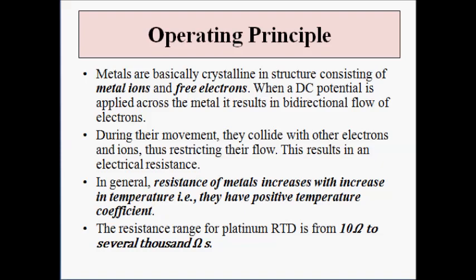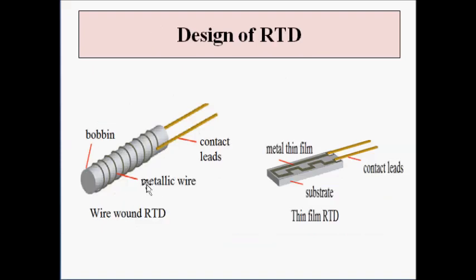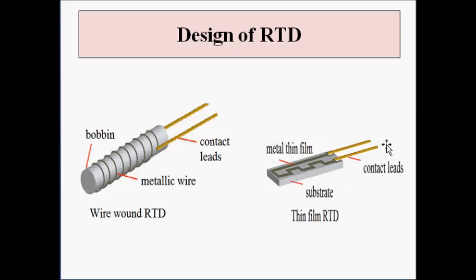RTDs are available in many configurations and designs. The two preferred configurations are: first, the wire wound type RTD, which consists of a bobbin with metallic platinum wire wound over it with two contact leads connected to the DC voltage source; and second, the thin film RTD, which consists of a substrate with thin films or layers of platinum or any other metal with contact leads connected to the DC voltage source.